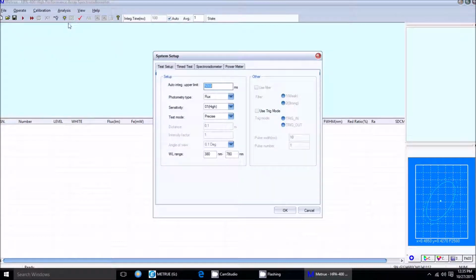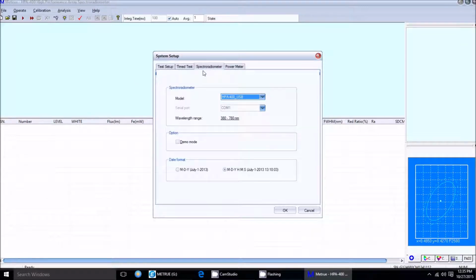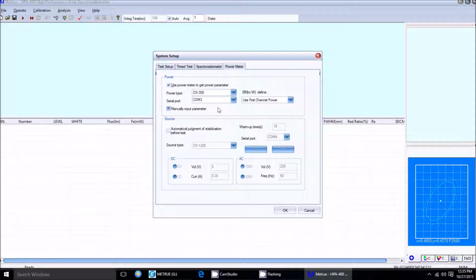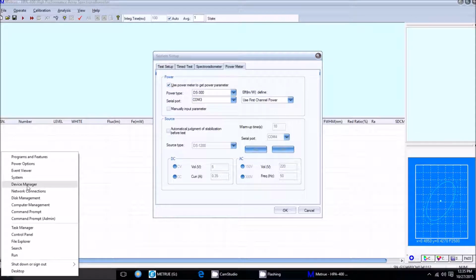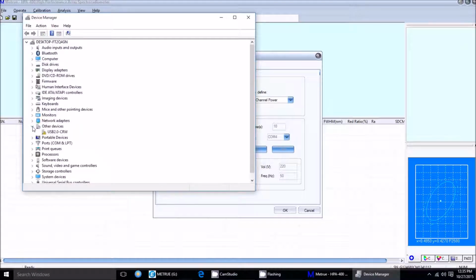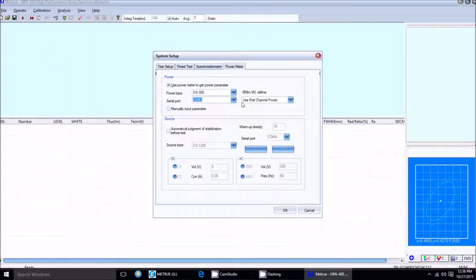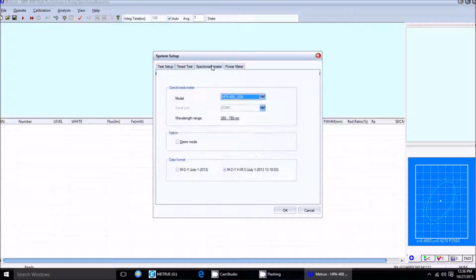So the first thing you want to do is system setup. And you'll want to make sure that everything is connected correctly. So this should be default. There's nothing you need to do here. But the power meter, DS300, for me, I have it to COM3. I think that's correct, but I can check by going back to my device manager. If I look at ports, I have a prolific USB to serial COM port. This is my RS-232 adapter, COM3. So this is correct. For you, it might be a different port. But for me, the first guess was the correct one. That's all I need to do there.